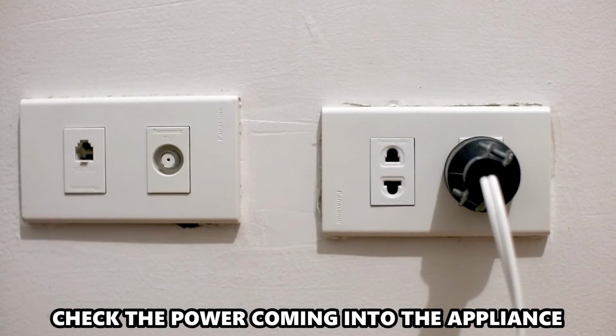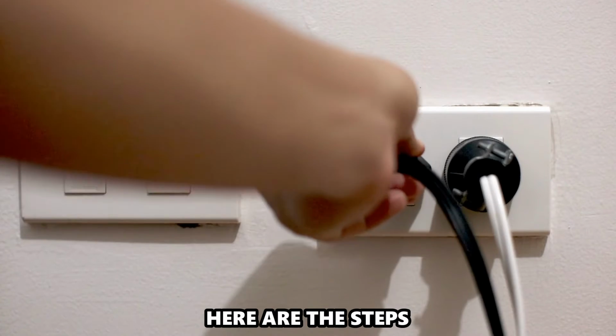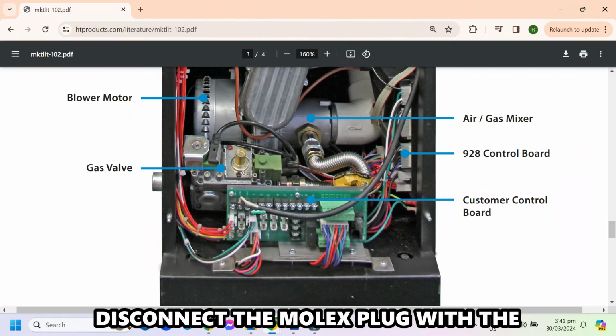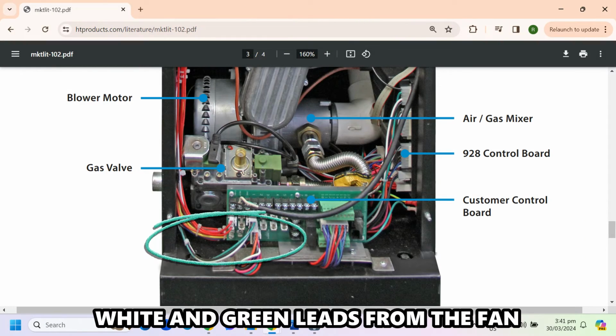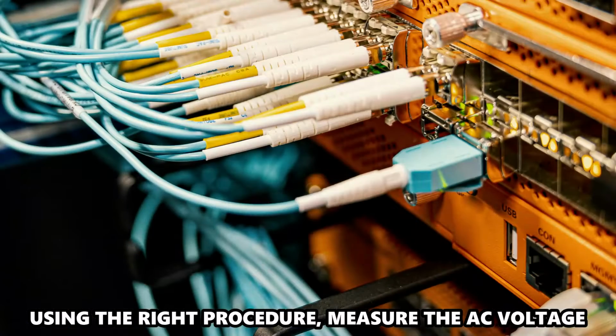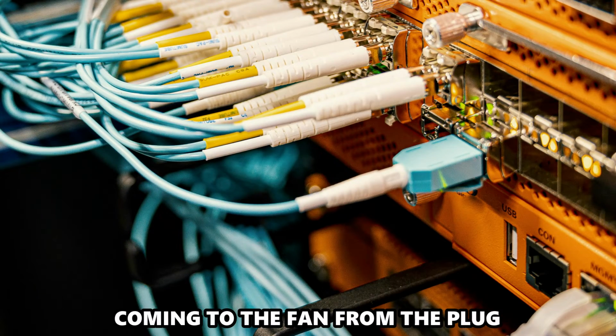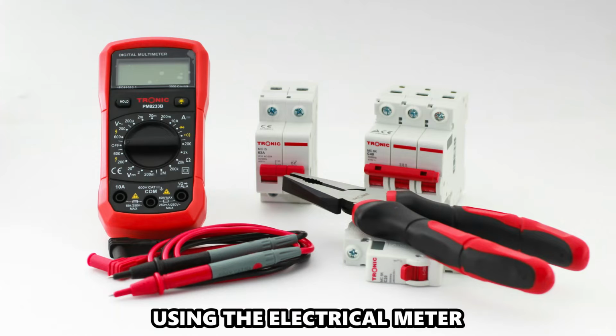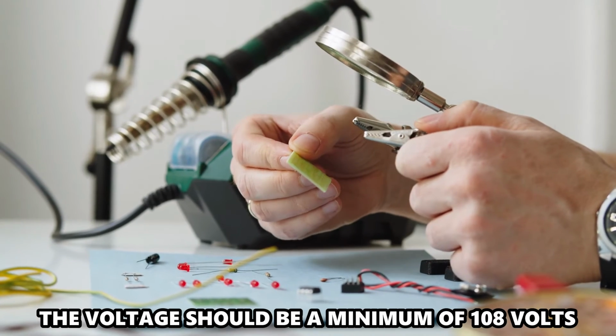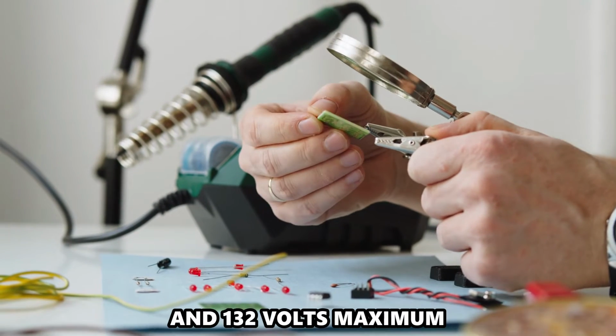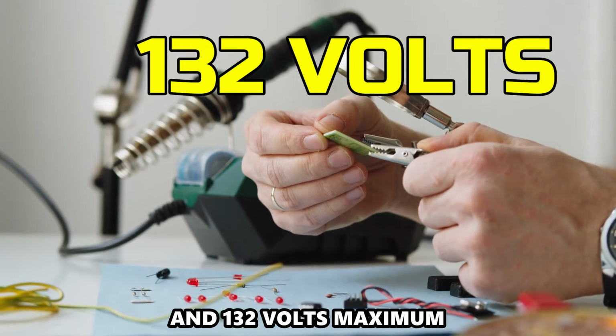Check the power coming into the appliance. Here are the steps: disconnect the Molex plug with the white and green leads from the fan. Using the right procedure, measure the AC voltage coming to the fan from the plug using the electrical meter. The voltage should be a minimum of 108 volts and 132 volts maximum.